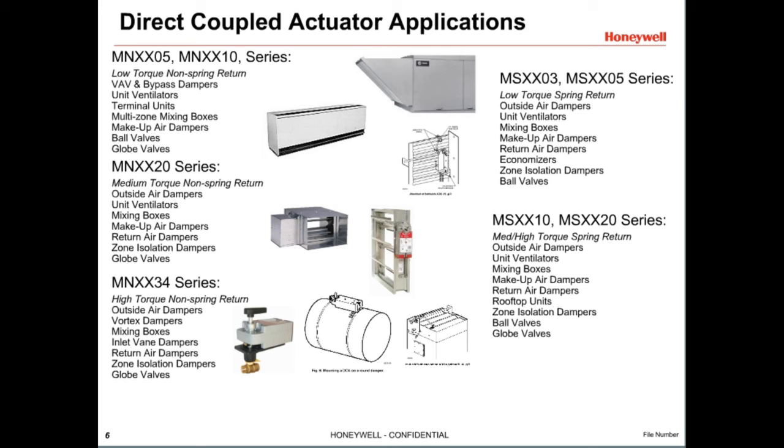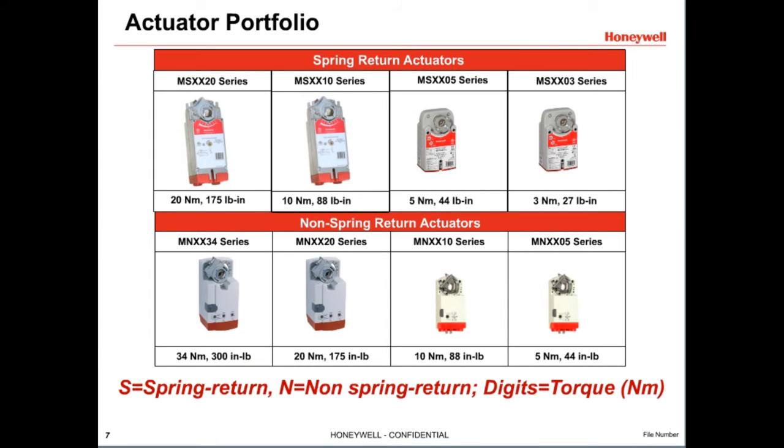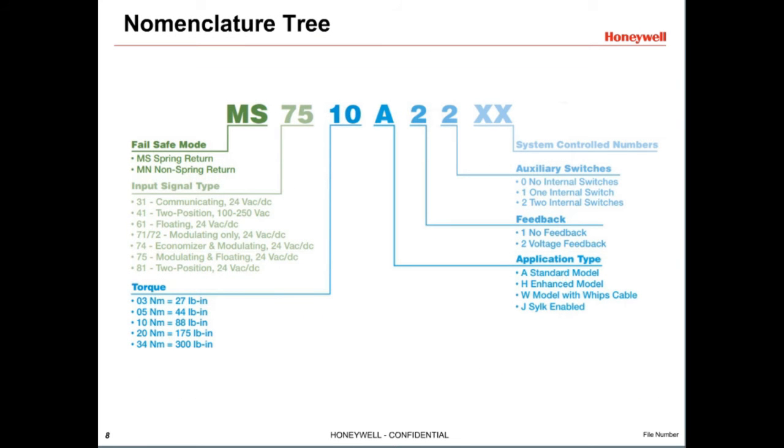Honeywell offers a full line of direct-coupled actuators available in models with and without spring return. The first letter M indicates it's a motor. The S and N indicate whether it's spring return or non-spring return — also referred to as fail-safe and non-fail-safe. The next two numbers indicate the type of control signal the actuator accepts: this may be on-off, two-position control, floating, proportional, or communicating. The next two digits specify the rated torque of the actuator in Newton meters.